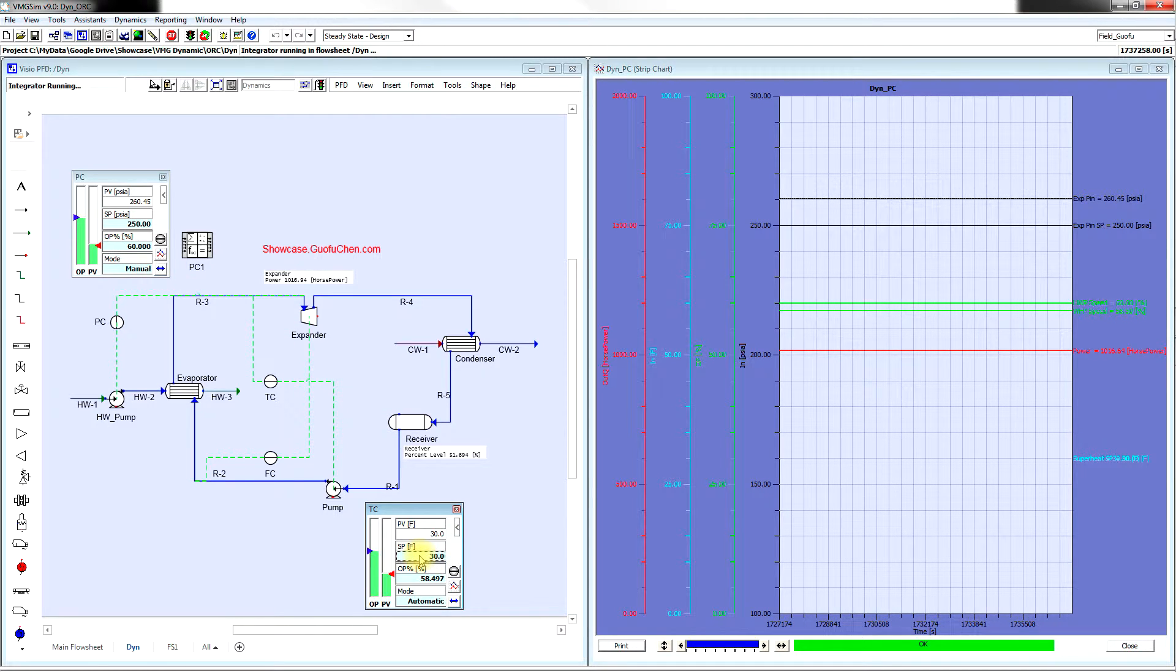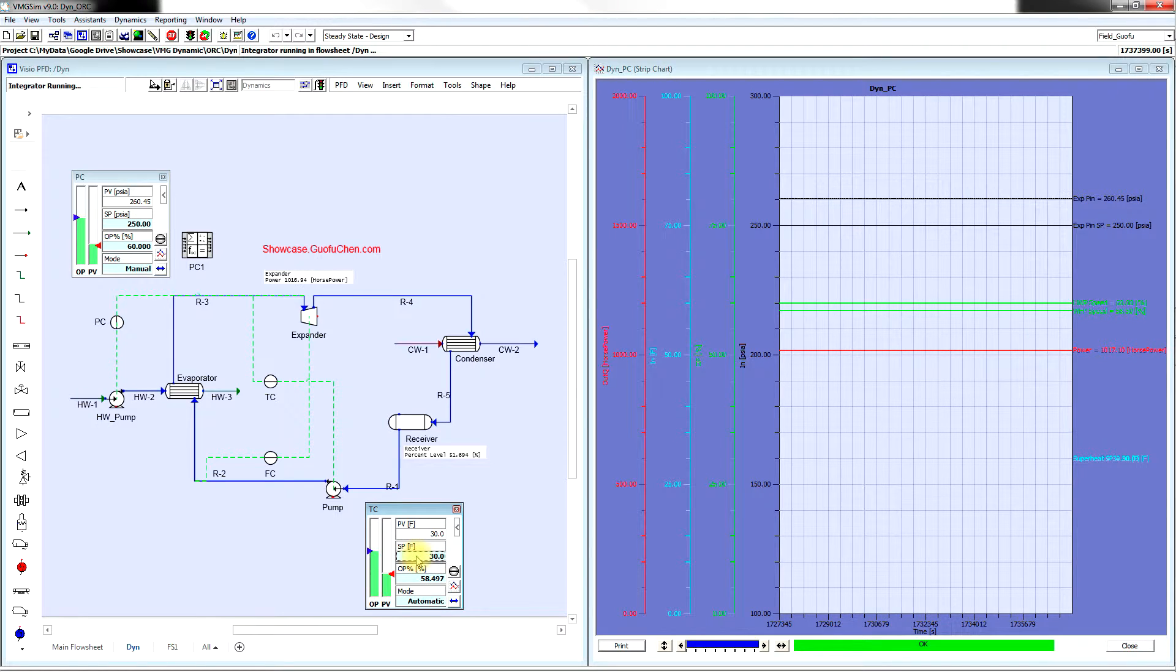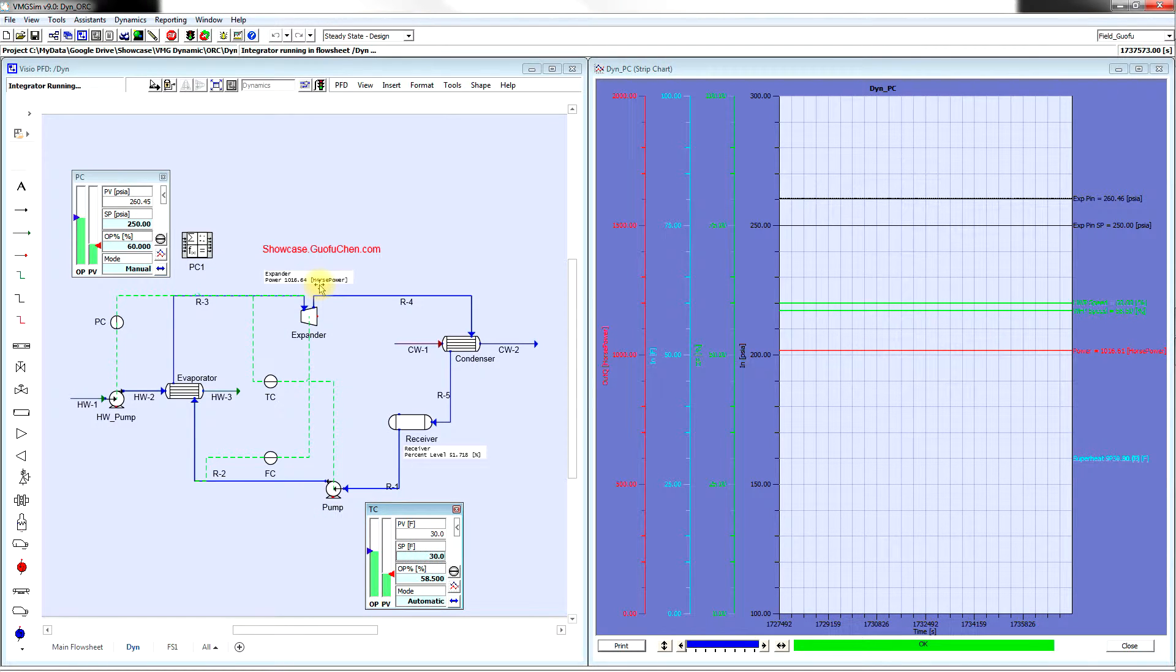Currently, the superheat of the expander inlet is about 30 Fahrenheit. The expander will produce about 1017 horsepower.